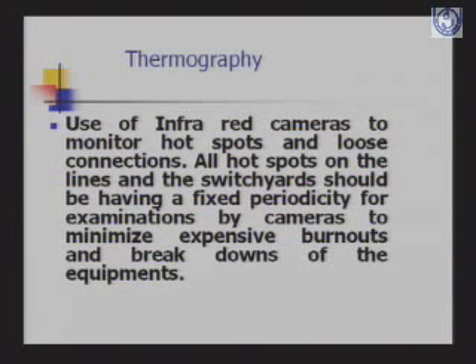So to find out where the bad joints are, we can now use thermography. Use of infrared cameras to monitor hot spots and loose connections can be made. Earlier these infrared cameras were being used only for transmission systems, but with the technological developments in the world, the cost of these infrared cameras has come down substantially, and these can now be used for distribution systems also. All hotspots on the lines in the switchyards should have a fixed periodicity for examination by cameras to minimize expensive burnouts and breakdowns of the equipments.